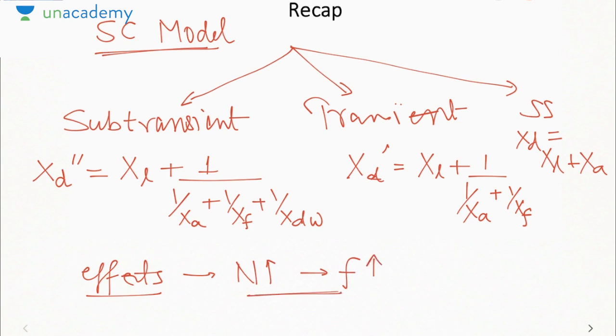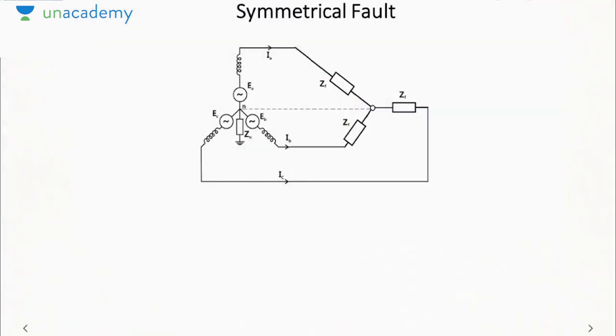In this lecture, we will discuss how to analyze symmetrical short circuit faults. That means the faults which are identical for all three phases, hence the system remains balanced. So in case of a symmetrical fault, the fault occurs symmetrically for all three phases, so the system will remain balanced. And in case of a balanced system, there are no negative or zero sequence components. Hence, we will discuss only the positive sequence elements. So let us discuss how to analyze this type of fault.